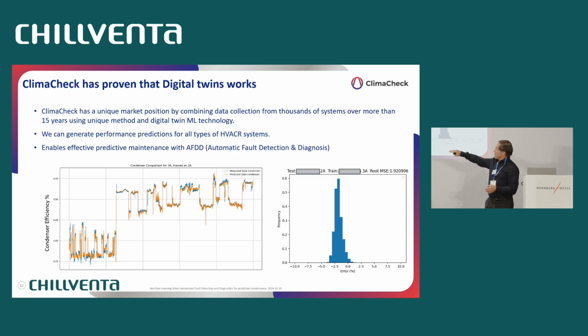So here you see at different capacity, you see how the condenser efficiency is changing between 75 and 95. So the more load I put on the condenser, of course, the efficiency goes down. So when it's 95, I'm using part load, and the condenser is really oversized for that. So it's really highly efficient at that. Okay, so then we see that the digital twin makes my life much easier. I can just trigger a deviation parameter rather than having to try to arrange warnings for that. And this is two different heat exchangers, two different units. And you can see that the deviation is about 1%, 1.5%. And this is including all sensor deviations and so on. So it becomes an extremely powerful tool.